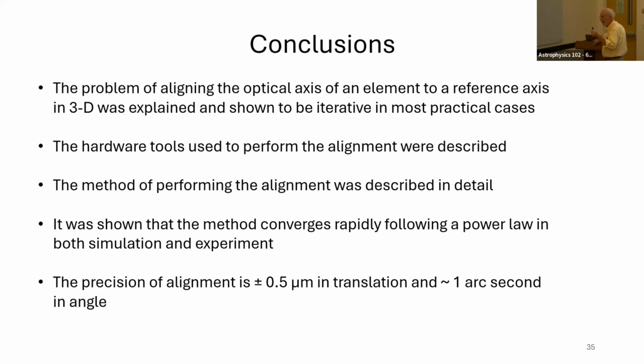I had a customer, somebody from Denver or from NOAA, who bought a PSM, called up and said, I think there's something wrong. He had a lens and then a plane mirror, and he was autocollimating off the plane mirror. He could see this sort of line image and thought something was wrong with the PSM. Thankfully, he sent me a picture of his test setup. I said, well, have you looked at whether your plane mirror is really flat? He said, oh, what's that? He went back, and yes, that was the problem. The setup was the problem.